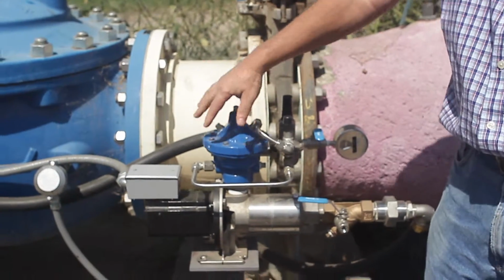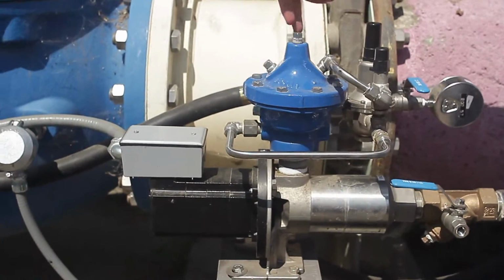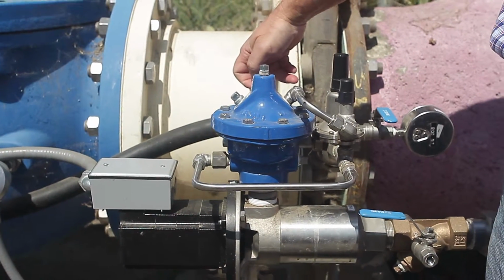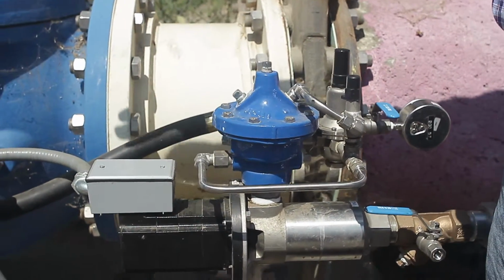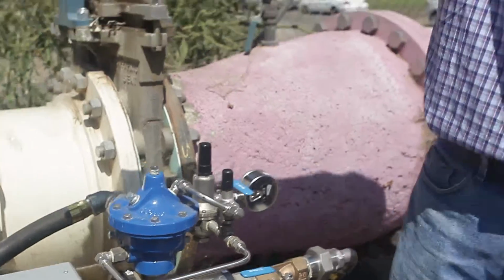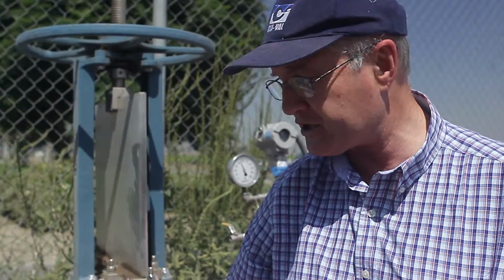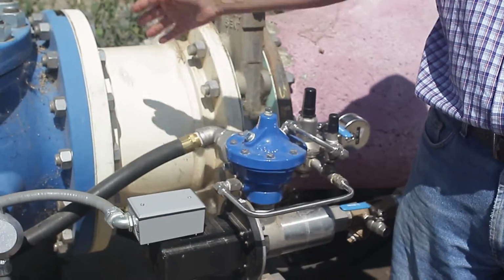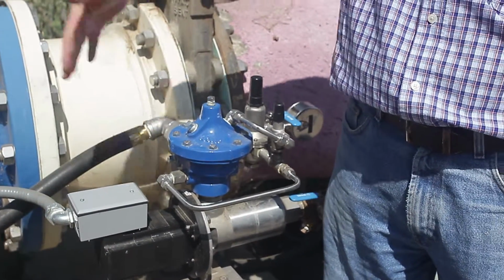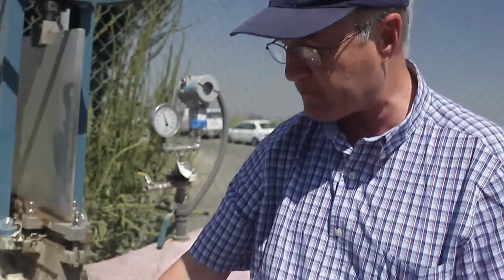The valve here, its purpose is to limit the downstream pressure. It's not likely, but if the demand goes very low downstream, or if they shut off the irrigation system completely, this valve will completely close and protect any piping from being overpressurized. That's the purpose of this valve right here.